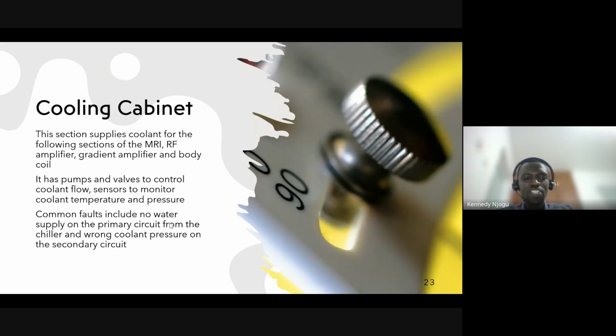The cooling cabinet is very key for the MRI. It's important to follow to the letter the service bulletin or technical information provided by the vendor. Most MRIs from different vendors use water, so the quality of the water is key. It's advisable to use deionized water, for example from a reverse osmosis plant, or purchased from companies that produce deionized water.